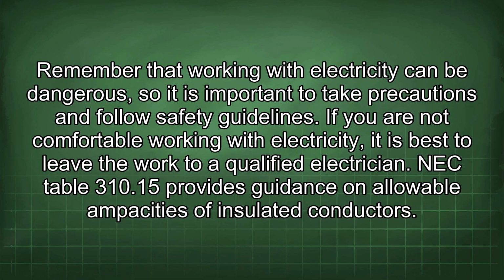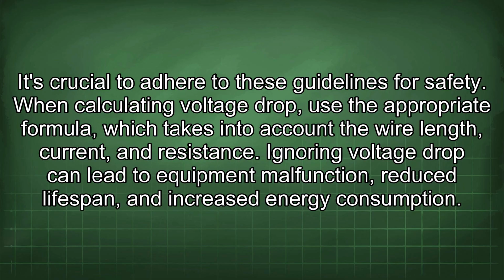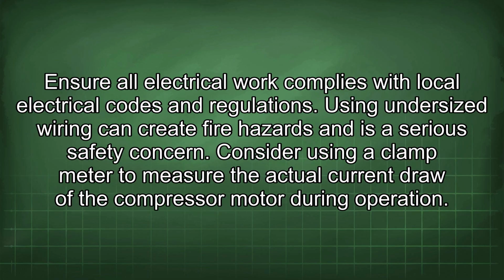NEC Table 310.15 provides guidance on allowable ampacities of insulated conductors. It's crucial to adhere to these guidelines for safety. When calculating voltage drop, use the appropriate formula which takes into account the wire length, current, and resistance. Ignoring voltage drop can lead to equipment malfunction, reduced lifespan, and increased energy consumption. Ensure all electrical work complies with local electrical codes and regulations. Using undersized wiring can create fire hazards and is a serious safety concern.